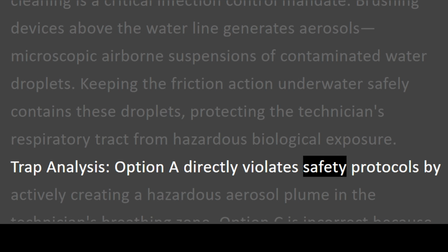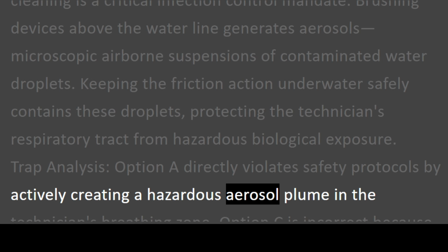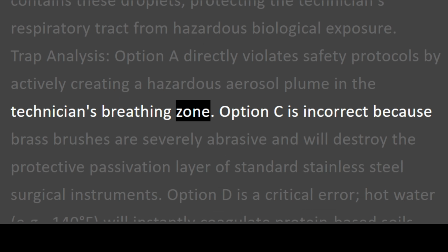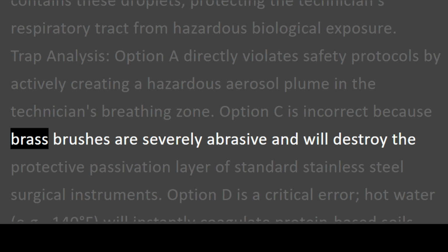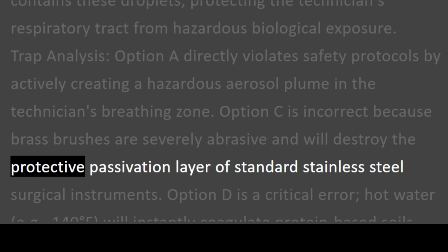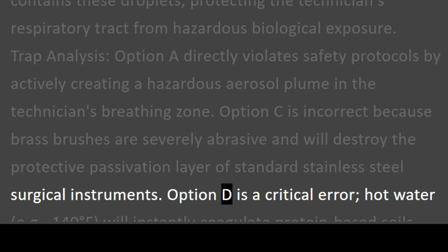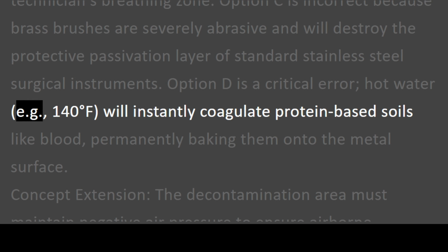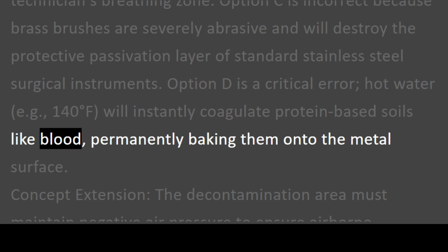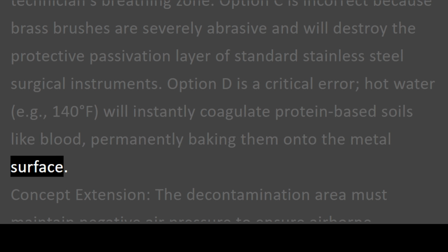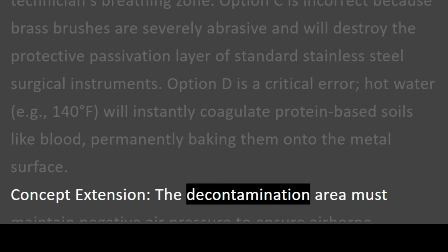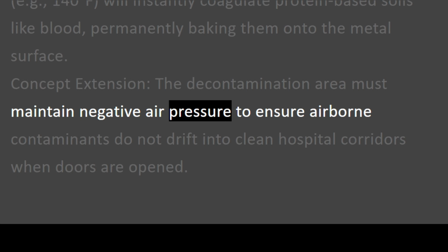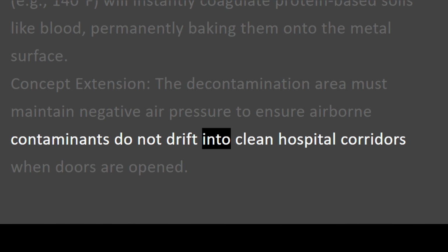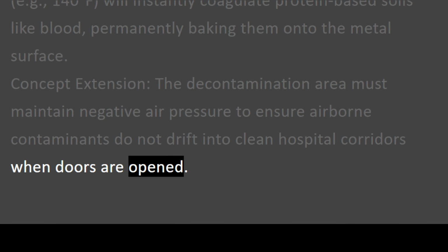Option A directly violates safety protocols by actively creating a hazardous aerosol plume in the technician's breathing zone. Option C is incorrect because brass brushes are severely abrasive and will destroy the protective passivation layer of standard stainless steel surgical instruments. Option D is a critical error. Hot water, e.g., 140 degrees Fahrenheit, will instantly coagulate protein-based soils like blood, permanently baking them onto the metal surface. Concept extension. The decontamination area must maintain negative air pressure to ensure airborne contaminants do not drift into clean hospital corridors when doors are opened.